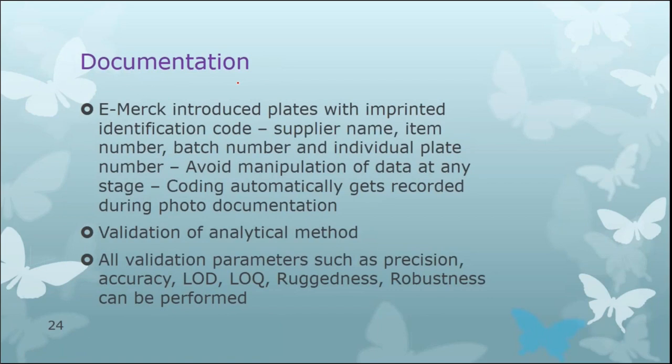For documentation, E-Merck plates are imprinted with an identification code including supplier name, item number, batch number, and individual plate number, avoiding data manipulation. This coding is automatically recorded during photo documentation. Validation of analytical methods can also be easily carried out — all validation parameters such as accuracy, LOD (limit of detection), LOQ (limit of quantification), precision, ruggedness, and robustness can be performed.